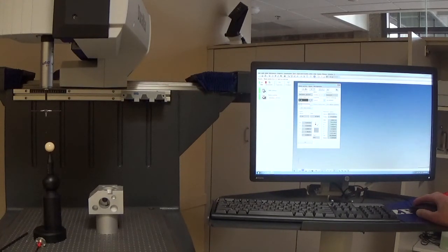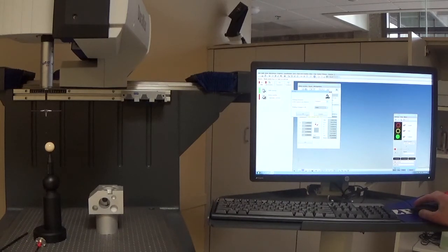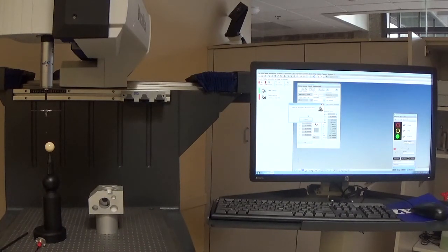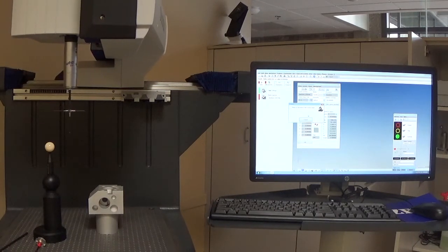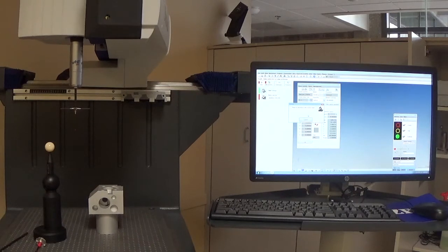Now we're going to click on that drop down and select number 5. And number 5 is our X minus stylus. We've got a red X here, so we know it's not qualified. So we click on the qualify stylus icon. We go through some confirmation windows, click OK. And now we need to probe that qualification sphere, which is just me telling the CMM or the stylus where that is so that it can measure.